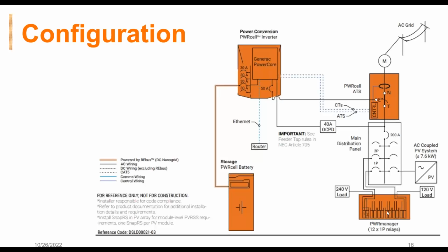Again, the way this device is installed is you're essentially mounting it below or near the main service panel, and then extending circuits from the main panel into the power manager's relays. There are 12 single-phase relays, so where you're mostly going to be connecting 2-pole breakers or two-phase loads, you'll run those conductors per breaker into 2 relays and then back into their breaker in the main service panel. It's an incredibly easy install, and again, it just adds so much functionality for homeowners.